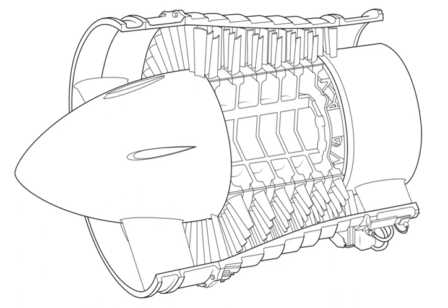The airfoil profiles are optimized and matched for specific velocities and turning. Although compressors can be run at other conditions with different flows, speeds, or pressure ratios, this can result in an efficiency penalty or even a partial or complete breakdown in flow, known as compressor stall and pressure surge respectively.